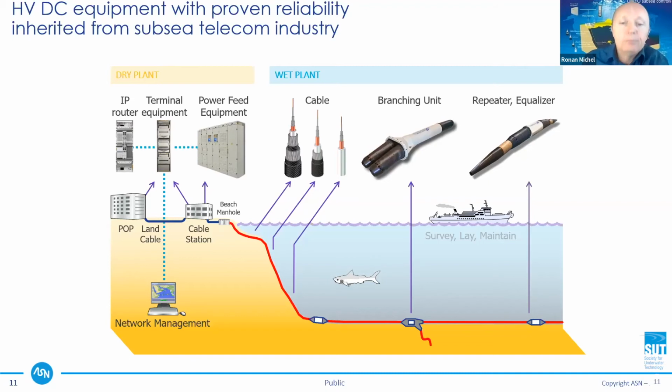Thanks to the series configuration, these systems are resilient to shunt faults, which means that you may have the cable damaged by a trawler, for example, with the copper exposed to water, but you can still energize end to end. Because you have power equipment at each end of the cable, you can still energize the power with 0 volt at the shunt fault, and you can still operate the telecom system fully. We are reusing this type of solution next for subsea control.